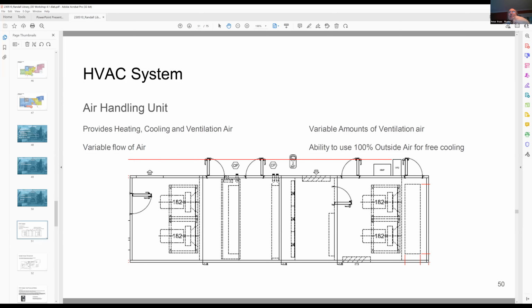This unit also has the ability to use what we call in the industry free cooling. It has the ability to bring in 100% outside air into the building. So when there are times throughout the year that are at the right temperature and conditions, we'll bring in 100% outside air and use no mechanical cooling or no mechanical heating. There are two purposes for that. Probably a night like tonight, right, Peter? Absolutely. This would be the perfect night to have some free cooling.